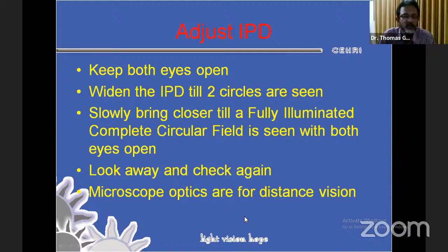Check again. Microscope optics are for distance vision, and even though when things are near your eye you tend to accommodate, to resist that you have to look away and look back into the microscope. I have seen people trying to do this by closing one eye at a time. But when you do that, when you're adjusting for IPD, you are actually doing a cover test on yourself. Your phorias will break. We may have intermittent divergence squints that are not cosmetically apparent, and all these would break, and it's not physiological. Once you start operating, things are different, and it's going to cause asthenopia or eye strain.